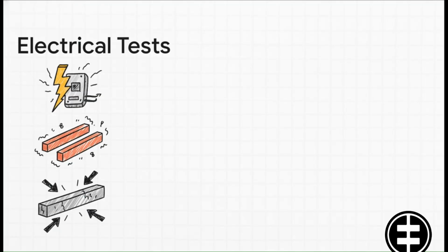Let me tell you, this trial is an absolute barrage. The assembly is basically blasted with 50 Hz dielectric tests just to check baseline insulation performance. Then comes the crazy part, simulated lightning strikes. We're talking massive impulse voltage waves. But it's not even just about the voltage, it's about the sheer physical force generated by electricity. The short circuit tests ensure that the bus bars, their supports, and the bracing devices don't just warp or shatter under the immense thermal and electrodynamic stress of a massive fault.